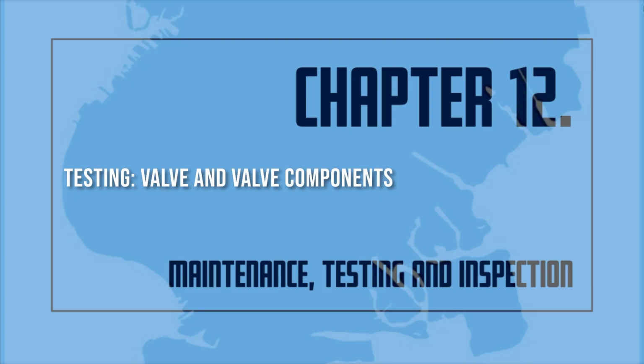Pre-action/deluge valves. The priming water level in supervised pre-action systems shall be tested quarterly in accordance with the manufacturer's instructions. Low air pressure alarms shall be tested quarterly in accordance with the manufacturer's instructions. Each deluge or pre-action valve shall be trip tested annually at full flow in warm weather and in accordance with the manufacturer's instructions. Protection shall be provided for any devices subject to damage by system discharge during tests. Dry pipe valve/quick opening devices. The priming water level shall be tested quarterly.